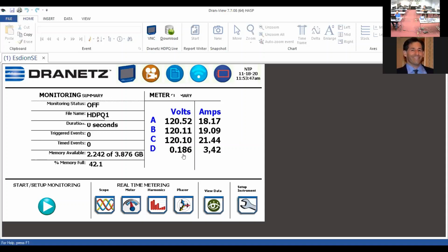The other method is establishing a communication link to the instrument and downloading the data via communication. This lends to the instrument's versatility, because the instrument might be in a remote location and you have a connection via wireless modem or something similar. The instrument supports wireless modems - it's virtually plug and play via the instrument's Ethernet port. So you can make a connection to the instrument to download data, or for remote setup changes, things of that nature.